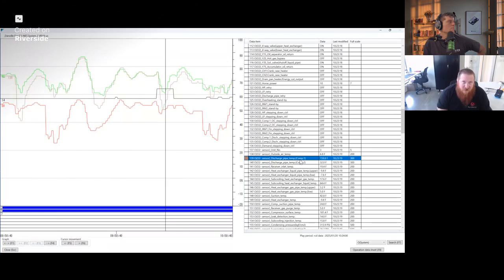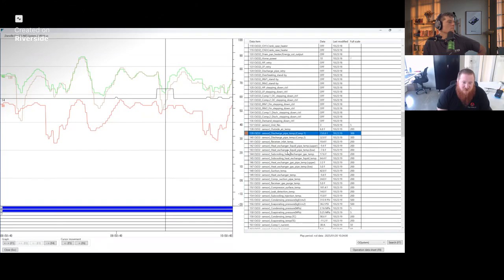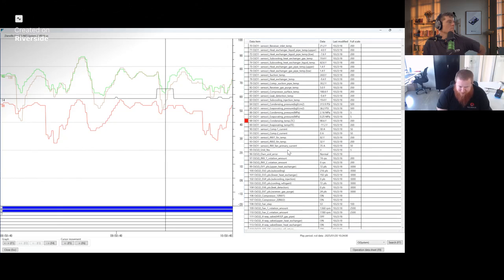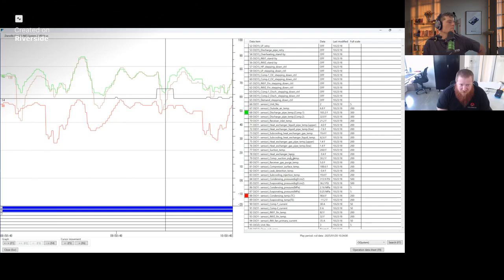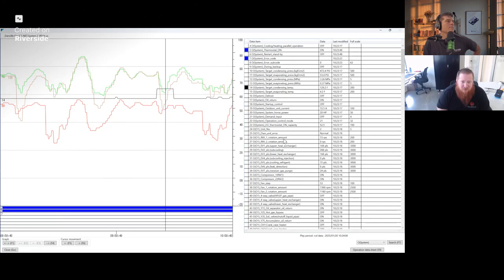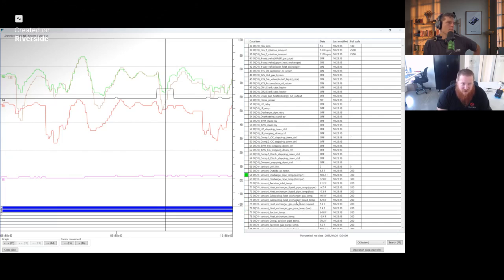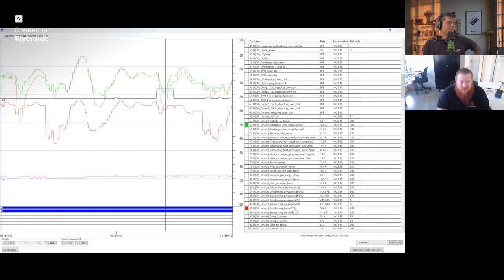Now, to go back to what Roman was saying, about why it's not ultimately important for that to take place: right off the bat, he got rid of the evaporator information. We don't care for the evaporator right now because we're in heating mode, but that doesn't mean that target's not going to line up. Even if that low pressure target lines up, there still could be an issue with something else in the machine. So it's irrelevant data to hang your hat on and say, hey, my target is met. Why do I care? It's all over the place too.